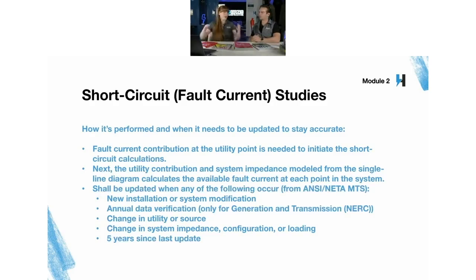And so that way you start somewhere with the available fault current, and then you know the impedance in your system. So at each point after an impedance component, it can calculate how much available fault current is left, essentially. Sure. Kind of. That's one way to put it. There's many ways to explain it, yes. Okay, and then the other part of it, when does it need to be updated? How do you keep it useful?